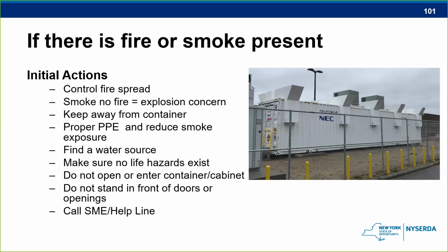hazard. And I have that in there. Do not open or enter that container. Do not stand in front of the doorway. If there was an explosion, you can see on top of this container in this picture here, the pressure is supposed to go up into the top areas in that deflagration venting area. That's just supposed to absorb all that pressure. But the doorway still could be a weak point, and we want to make sure that those doorways are not actually coming off and hitting one of our firefighters. So make sure that the firefighters are not standing in line of sight of those doorways where they can actually blow off and hit one of the firefighters.